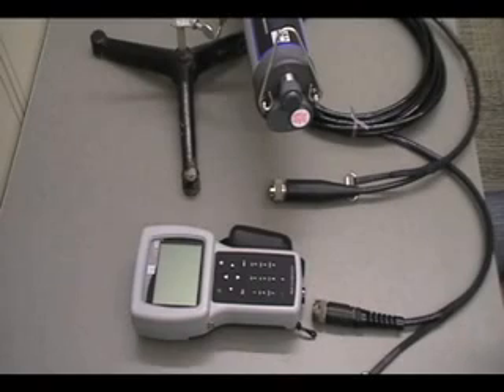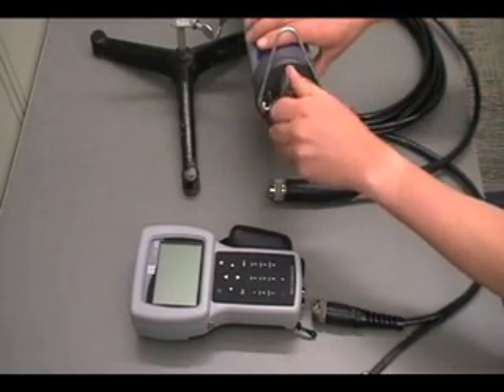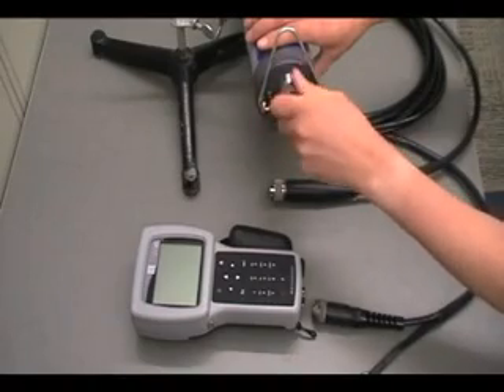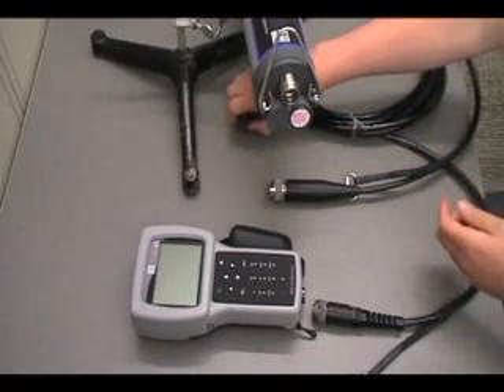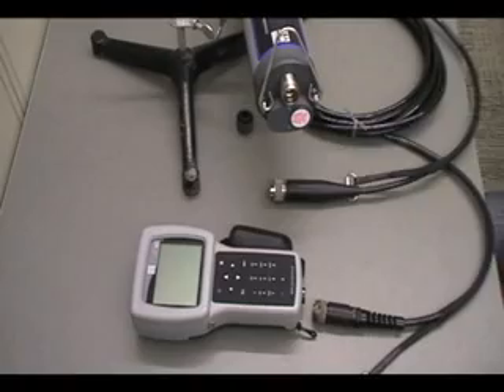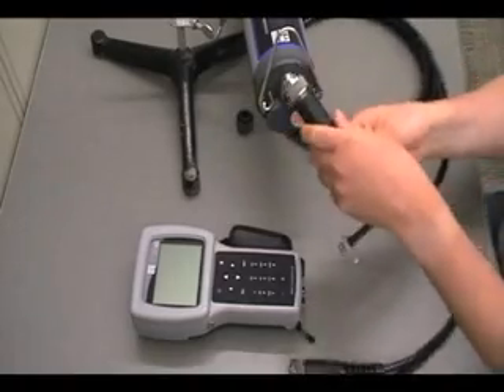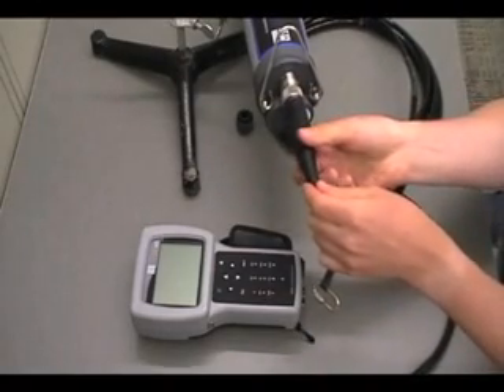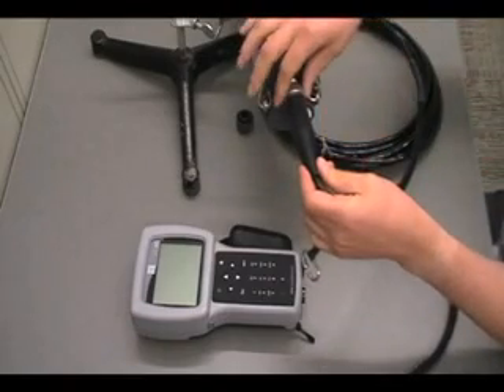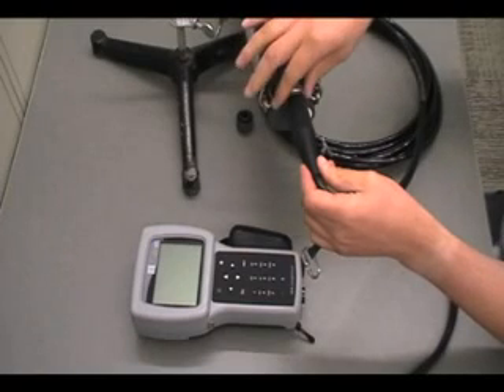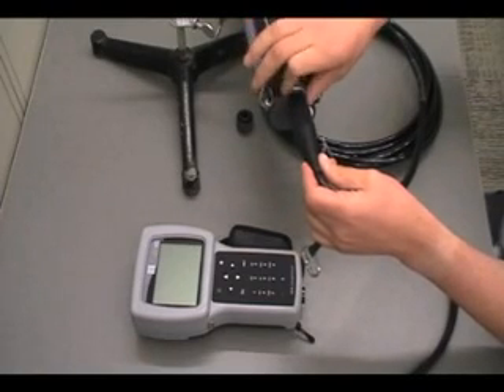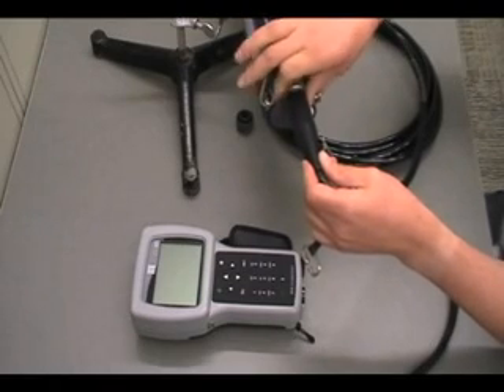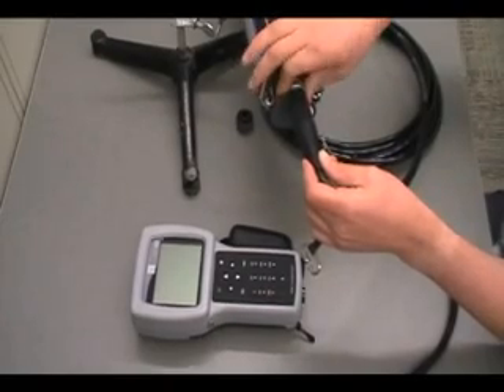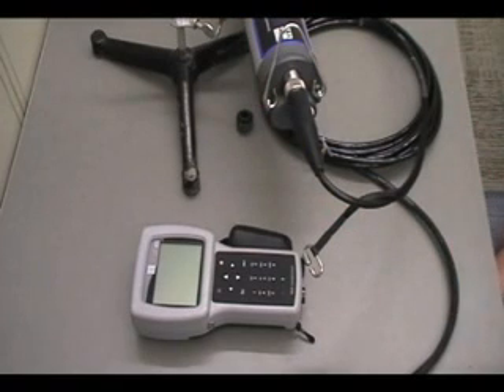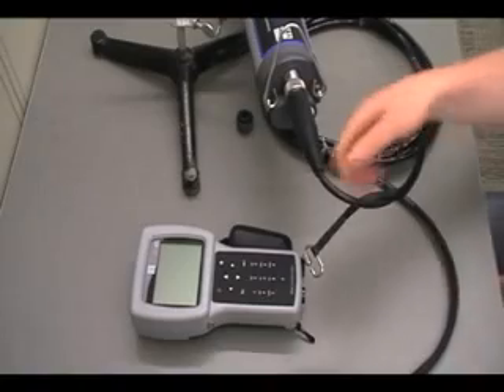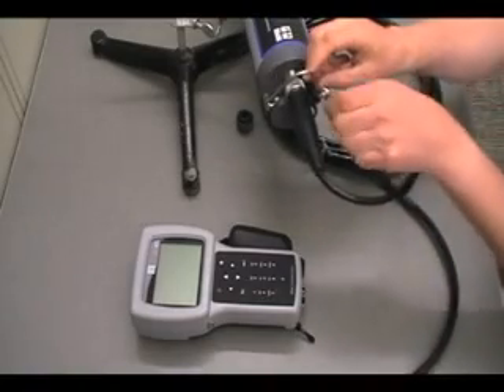Step 1. Remove the waterproof cap from the sonde connector. Do not discard this cap. You will need this cap for later deployment and long-term storage. Step 2. Connect the field cable to the sonde connector. There is a guide inside the connection that ensures that the pins are properly lined up. Rotate the cable gently until the guide engages. Step 3. Tighten the connector by turning clockwise. When connected properly, only 2 threads should be visible. Step 4. Attach the strain relief connector to the metal handle and close the connector's opening.